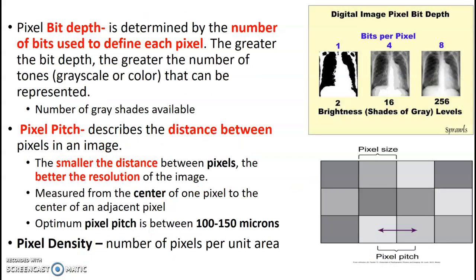Pixel bit depth is the number of bits used to define each pixel. The greater the bit depth, the greater the number of tones that can be represented. Pixel pitch describes the distance between pixels on the image, measured from the center of one pixel to the center of an adjacent pixel — the smaller the distance, the better your resolution. Pixel density is the number of pixels per unit area.